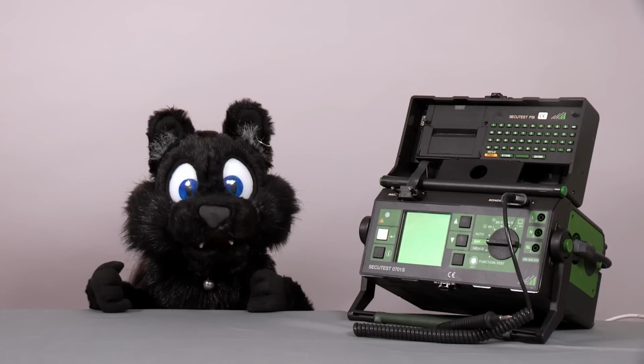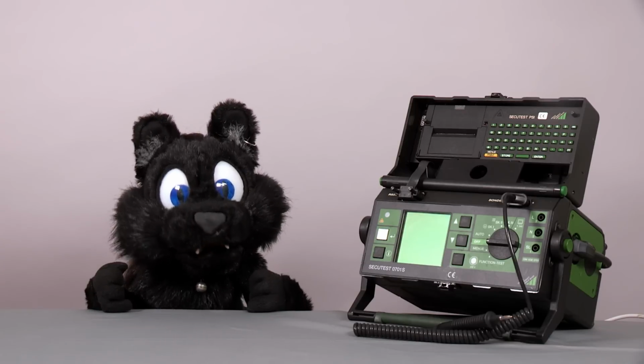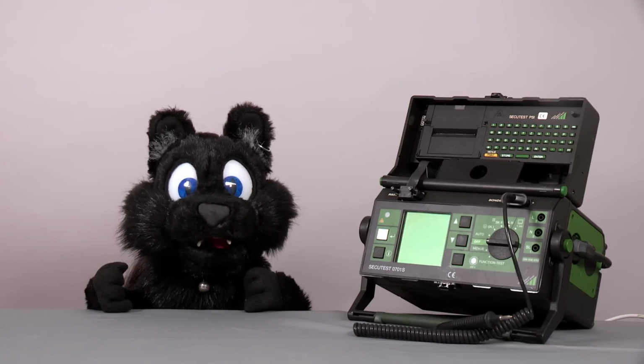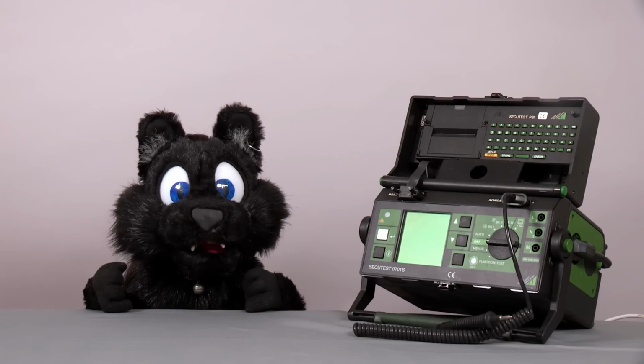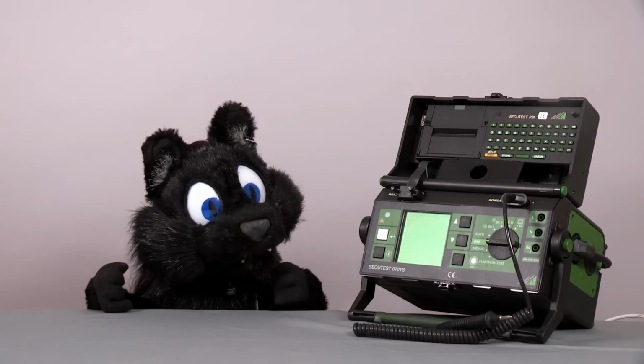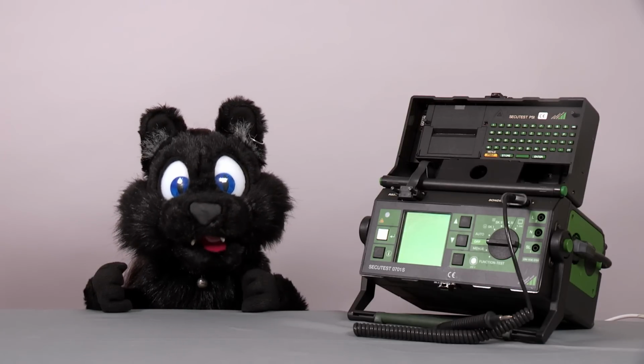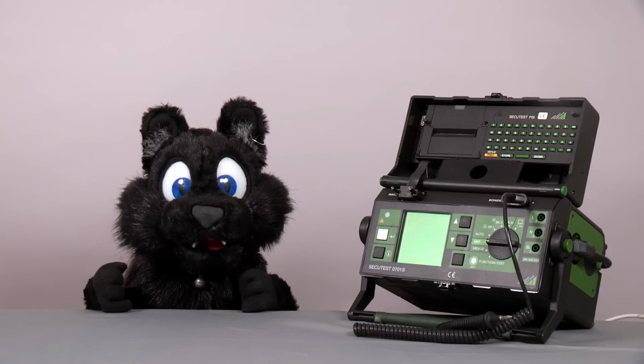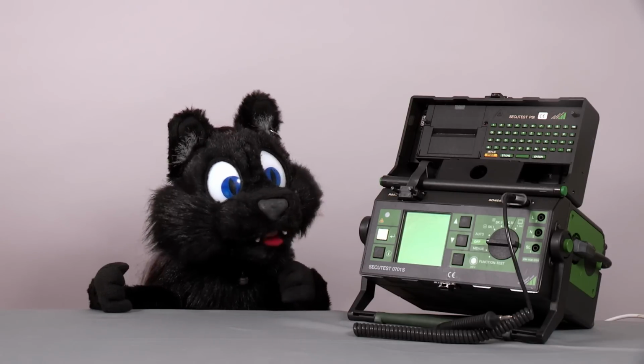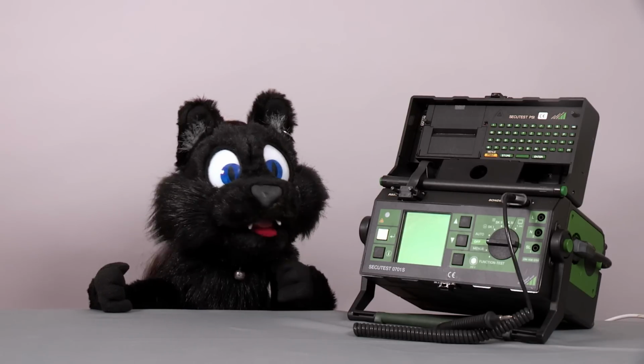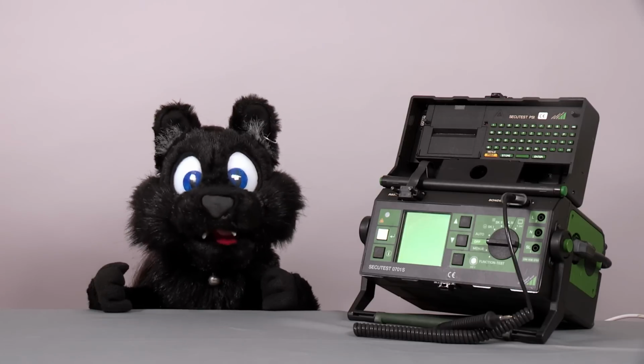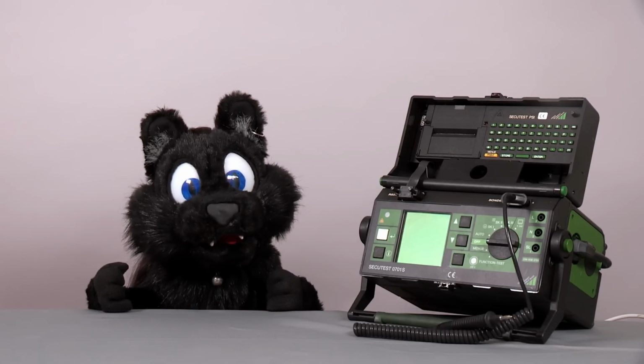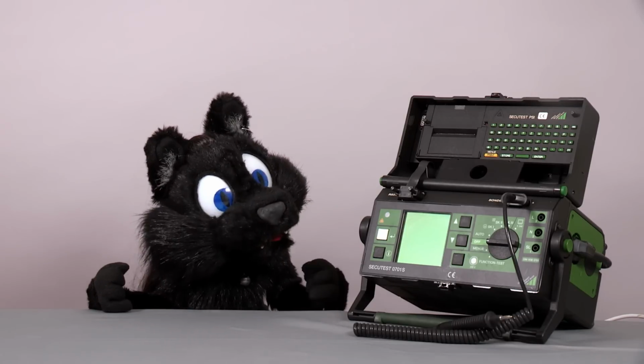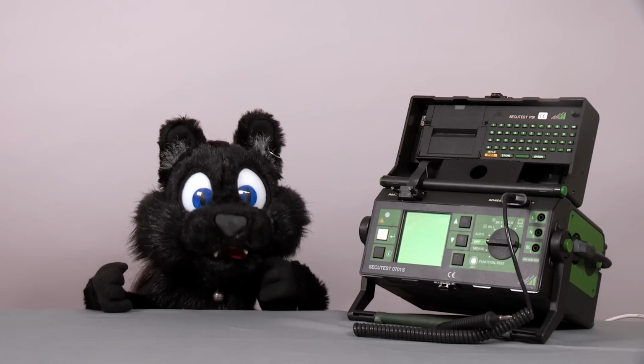I only skimmed over the specs, but it boils down to a visual inspection followed by measuring the earthing and insulation of the devices. This tester here is an all-in-one solution for the 701 and 702 tests. It seems to be a first-generation model, since the current model range does not include this one. And the price range is clearly, if you have to ask, you can't afford it.